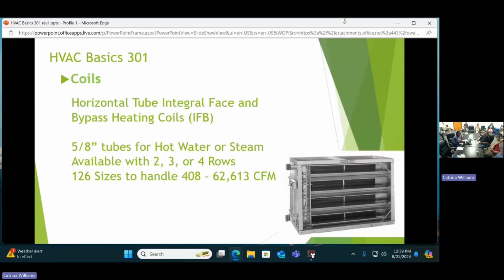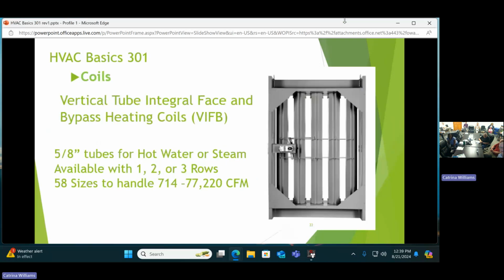Let me back up a little bit to show you this. In this particular case, you're seeing the horizontal with the full face. All the air would go through the element in this case. The bypass is fully closed. This next picture shows a VIFB, and that's just the opposite. We're showing it now with full bypass. The elements are protected. They ship out this way to protect the elements during shipping so you don't get damage on the road. That's just what they're showing in the picture, the full bypass and the heating elements all closed up. Again, we're using 5/8" tubes.